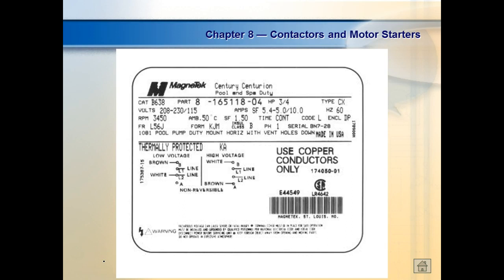To plug a motor, it's got to have a real high service factor. We'd never plug a motor that's got a 1.0 service factor. You could mess it up, because it's going to pull start current for a long time. So the term plugging a motor means you reverse the direction of the motor without letting it come to a complete stop. Anybody got ceiling fans? You ever plug it? You hear that thing hum at you? And those things have overloads in them too. It's a wonder they don't trip out all the time.